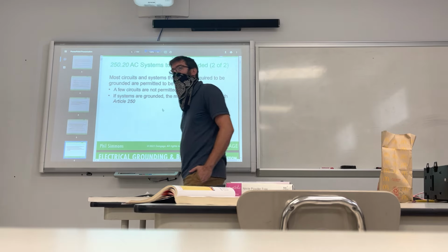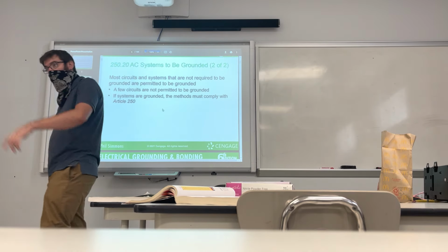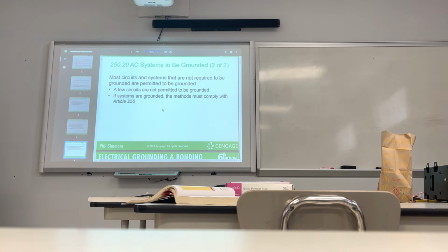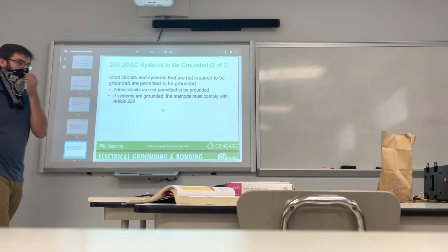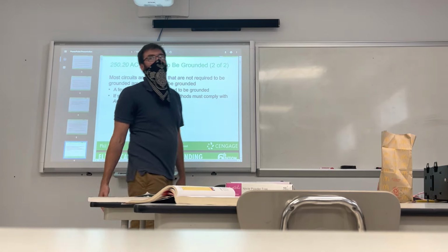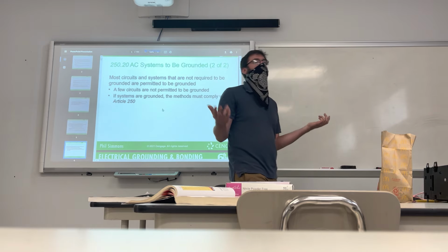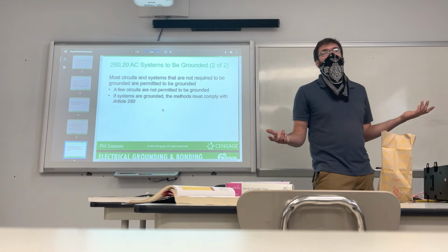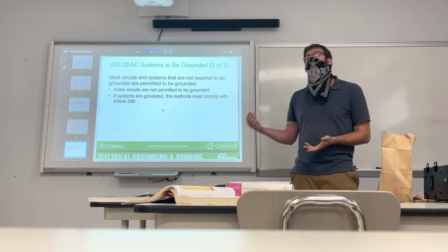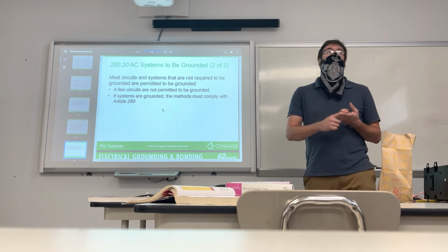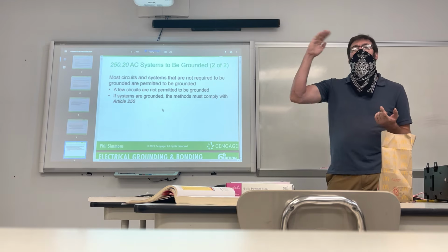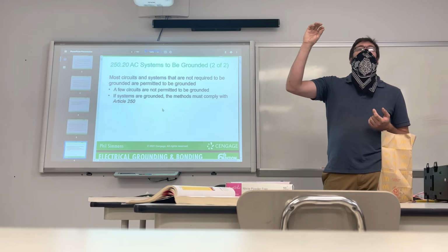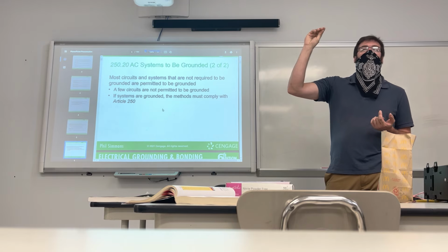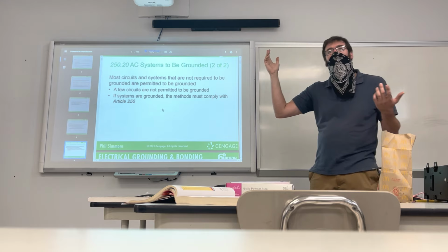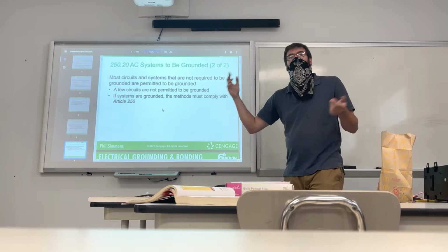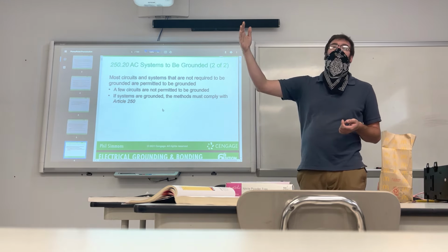How about something dealing with like a big, what? Like machinery or something that has to run all the time. Yes, something that you really want running all the time. And like we said about conduit, what kind of challenge does it present? Things could go wrong with conduit, can't they? Especially if something is vibrating, or if that wire was improperly installed, because is there a chance that after years of that wire shaking in the conduit, its insulation can be eroded away? Sure it can. And if there's a chance that it can be eroded away, there's a chance that it can hit the side of the conduit, right?